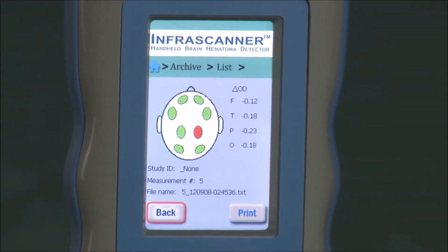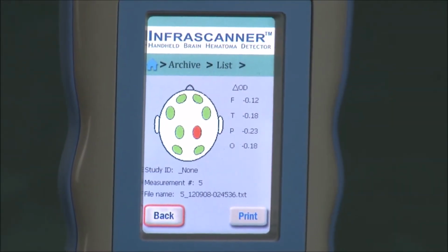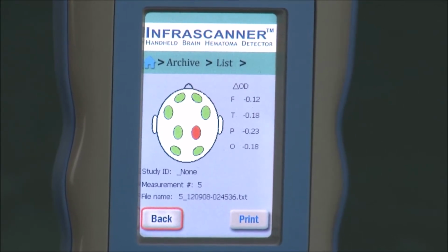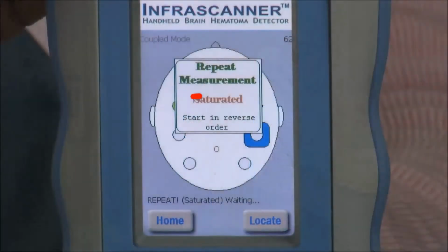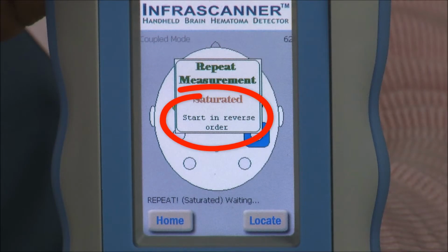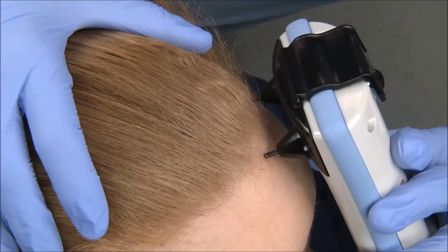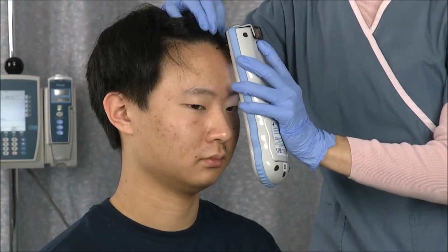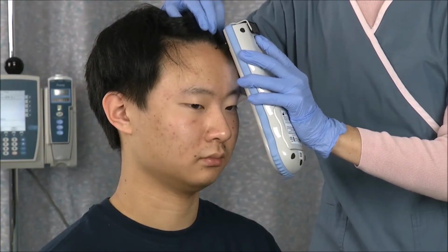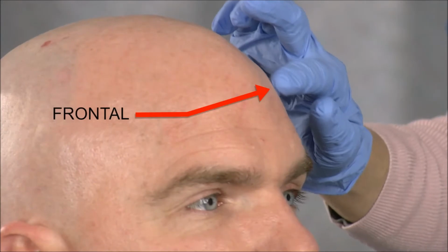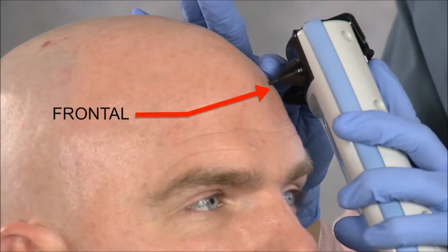There are 4 measurements that must be recorded on both sides of the patient's head for a total of 8 measurement results. You always begin on the left side of the head for each measurement, unless the infrascanner tells you to reverse the order. The 2 frontal measurements are taken just under the hairline, with the probe closest to the patient's nose lining up directly above the appropriate pupil.